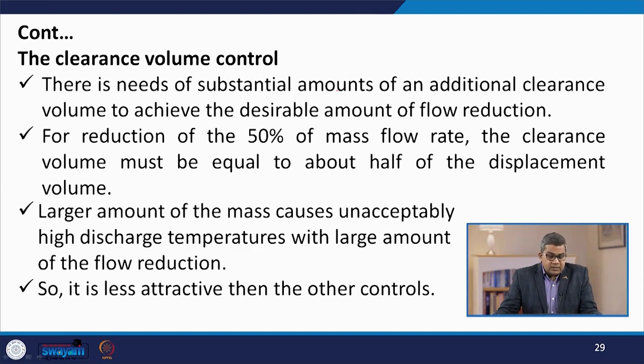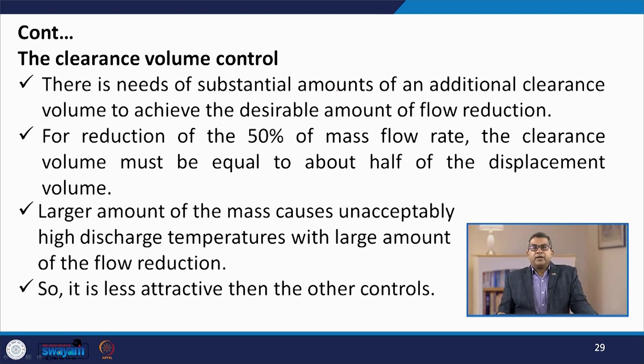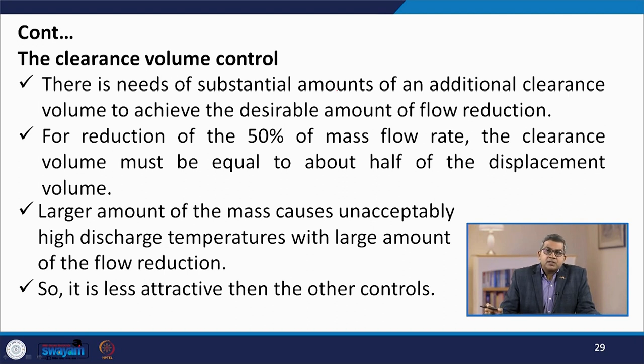Clearance volume control requires a substantial amount of additional clearance volume to achieve the desired flow reduction. For a 50% reduction in mass flow rate, the clearance volume must equal about half of the displacement volume. Larger amounts may cause unacceptably high discharge temperatures with large flow reduction, making this less attractive than other controls.